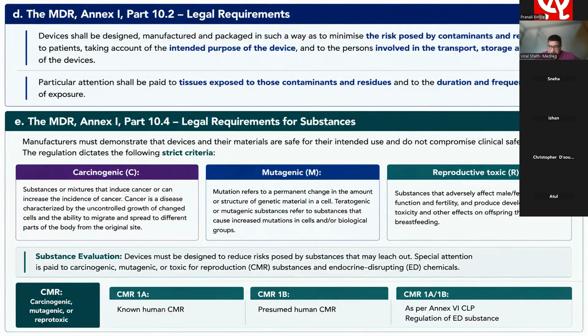So generally in that industry, the plastic tubings are made with PVC resins and some plasticizers. So DOP is one of the plasticizers. So either you can replace it with other plasticizers, so you can claim DEHP free. And if you still want to incorporate those CMR substances, then you must ensure the weight that is recommended in MDR.